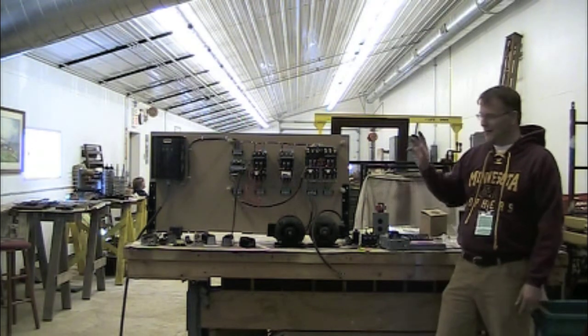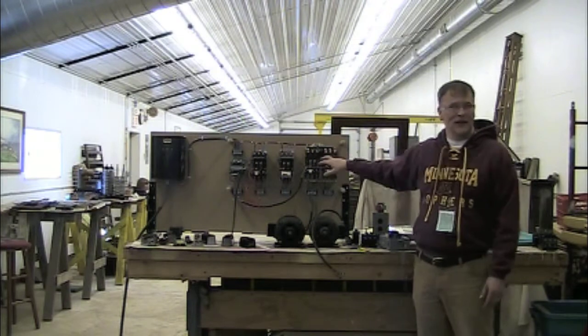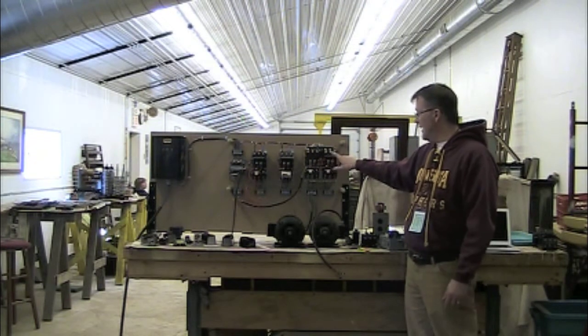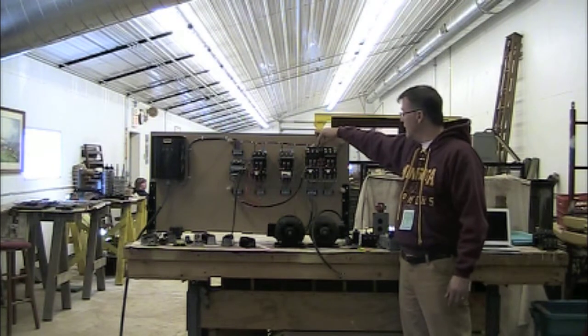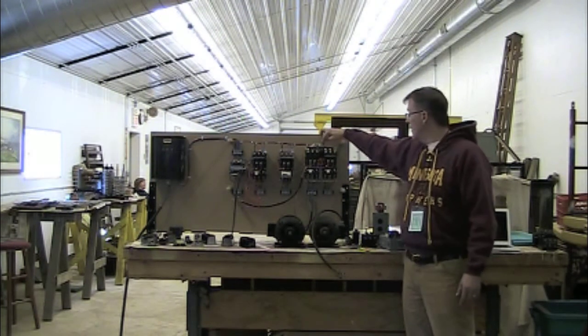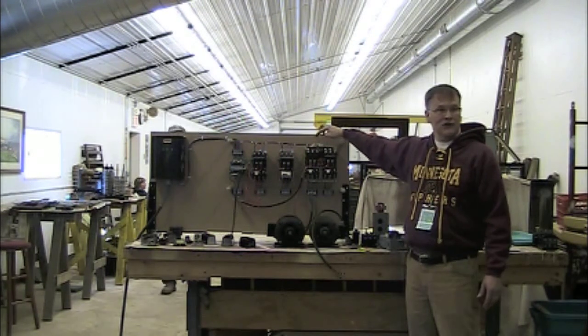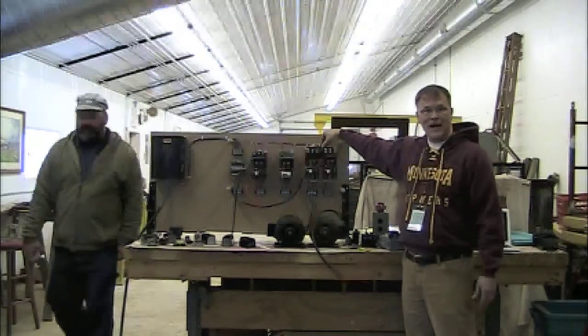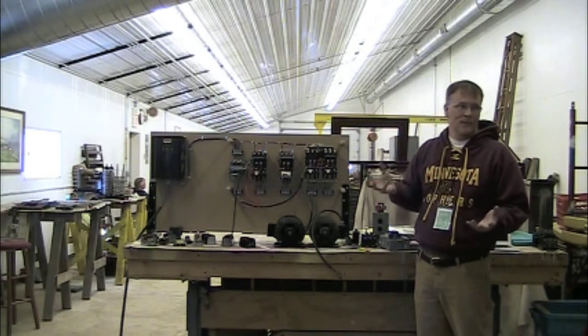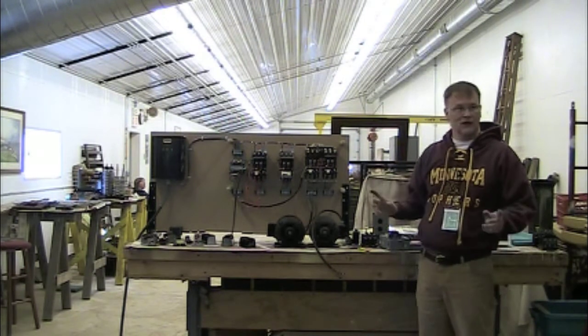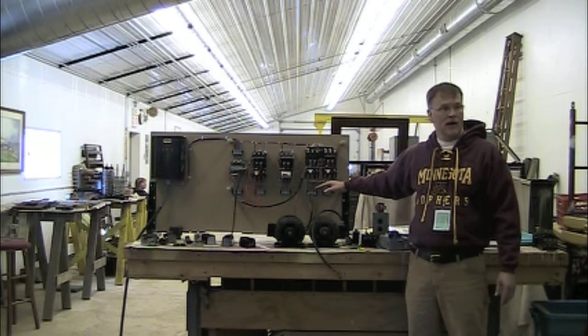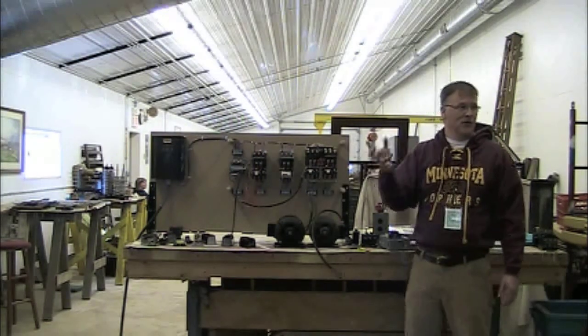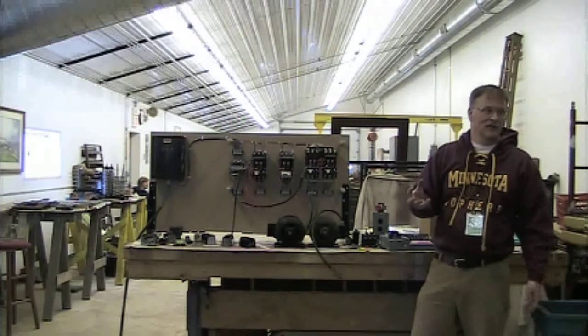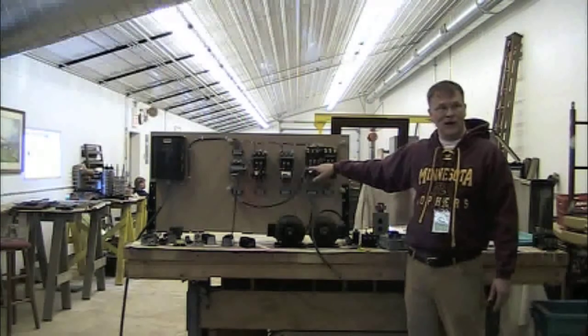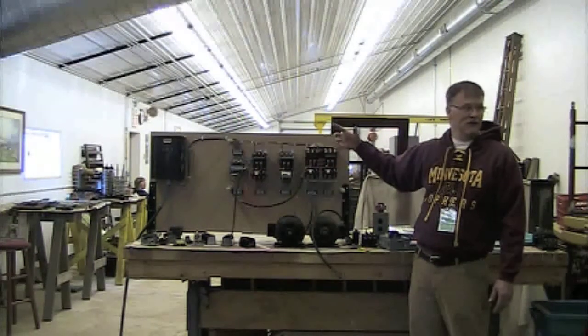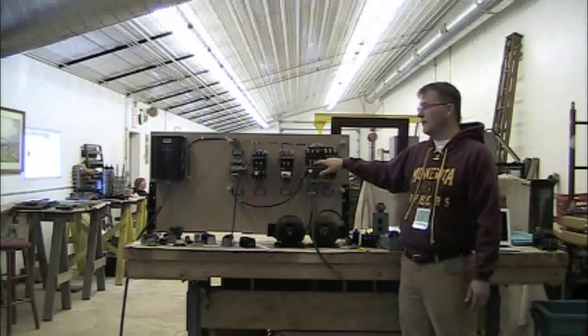I don't remember the number on the reversing one, but the reversing ones are almost identical to this. It has the interlock and the extra control relays, and then these things actually interchange the power lead. So L1 is going to go to L3, L2 to L2, and so this set of jumpers on the top is a different set because it's interchanging the leads, but otherwise it's basically the same. You have an interlock and you're controlling them separately, and then off the bottom they're going to have one overload block because your motor is just reversing, the current draw is the same. There's no reason to have 2 sets of heaters. On this one, it's for a separate winding motor that's going to have different current draw, different full load amp values for each winding, so it has a separate overload block for each of them.